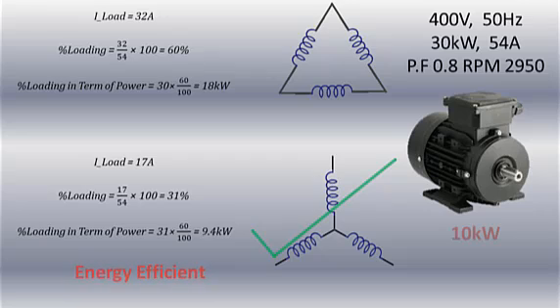As long as the load is below 10 kilowatt, to optimize performance and improve energy efficiency, you can either choose a different motor more suited to the load or run this motor in star configuration.